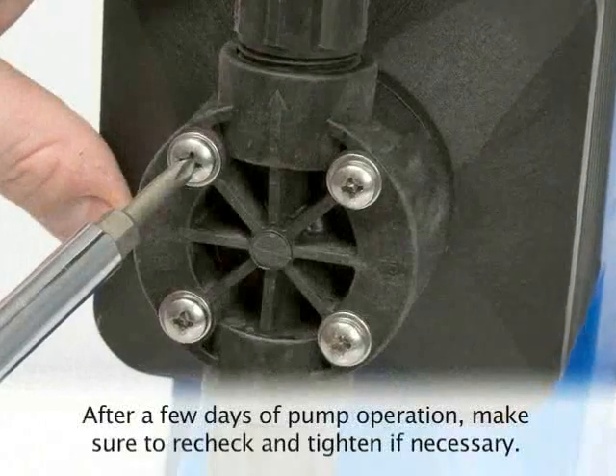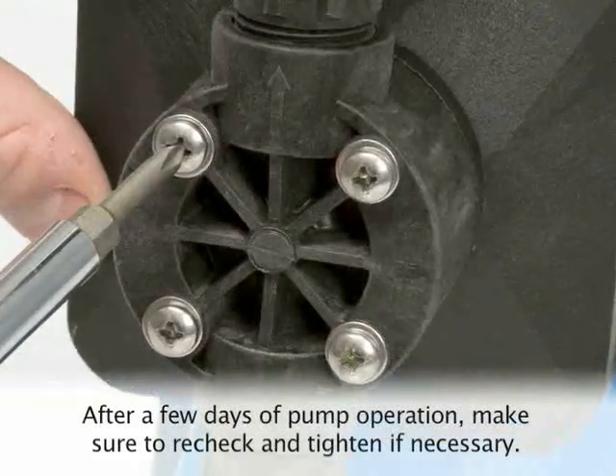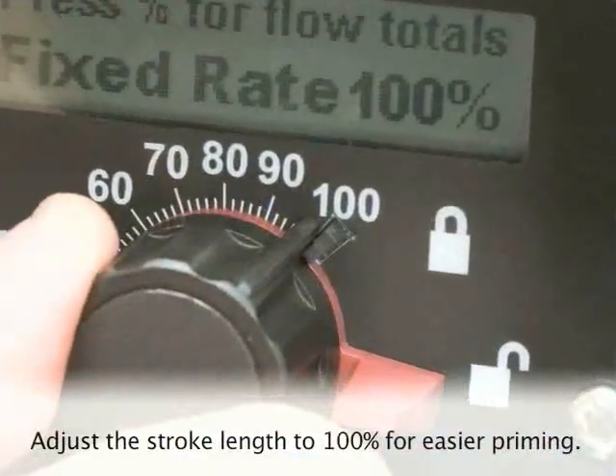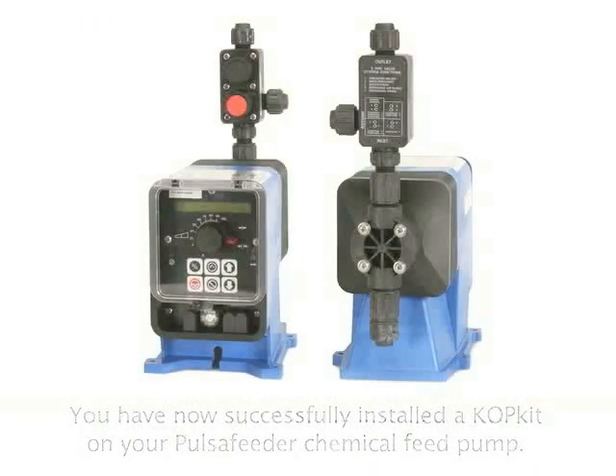After a few days of pump operation, make sure to go back and recheck the head screws and re-tighten them if necessary. Reinstall the suction tubing and foot valve and test the pump with water. Adjust your stroke length to 100% for easier priming. You have now successfully installed the KOPkit on your Pulsafeeder chemical feed pump.